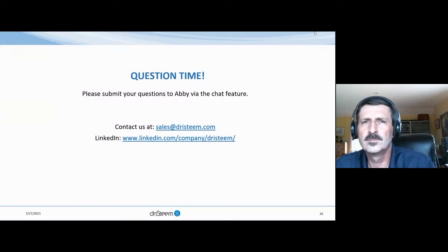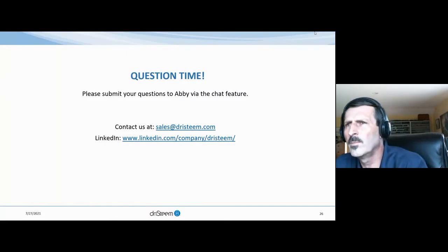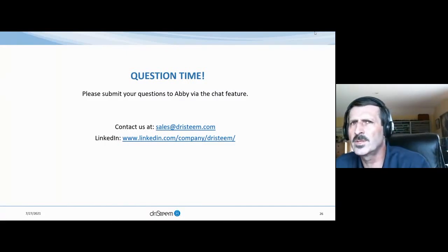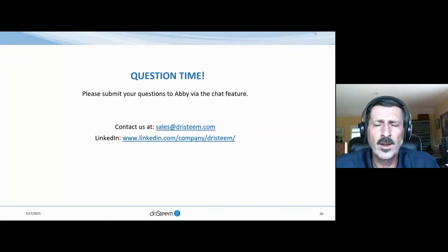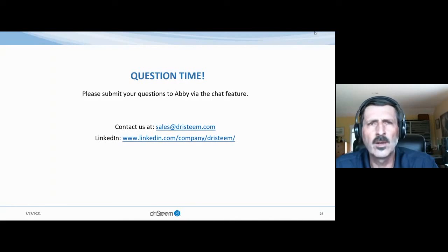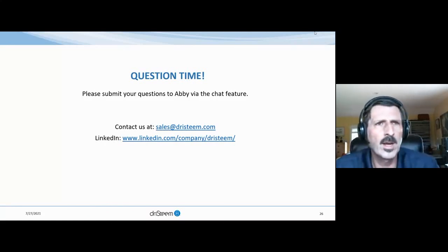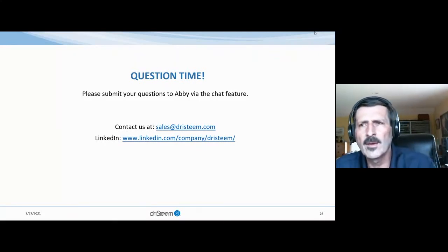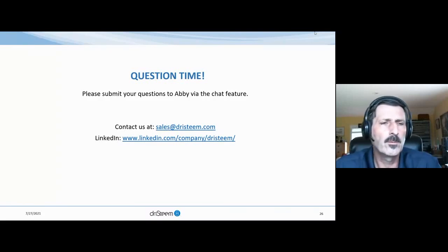We have one more. Does DriSteem have an ultrasonic humidifier option? If not, could you explain why DriSteem's approach is preferred? Ultrasonic units are actually under development. However, at this point, we deem ultrasonic to be generally fairly high maintenance, and we've been discussing applications and requirements where we're looking, number one, at high hygiene, and number two, at high reliability and low maintenance. Ultrasonic units can be problematic with respect to maintenance and also with respect to hygiene, so they do require a higher degree of care. For that reason, we generally will advocate clean steam or hygienic systems like our high pressure units with appropriate water treatment.